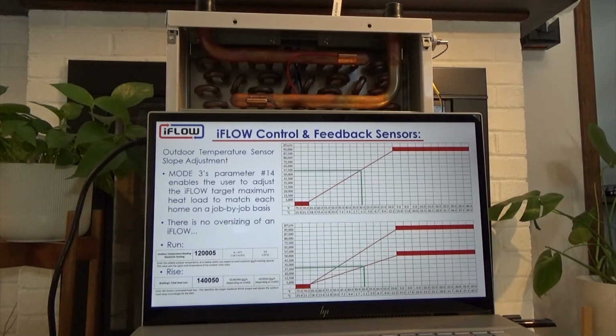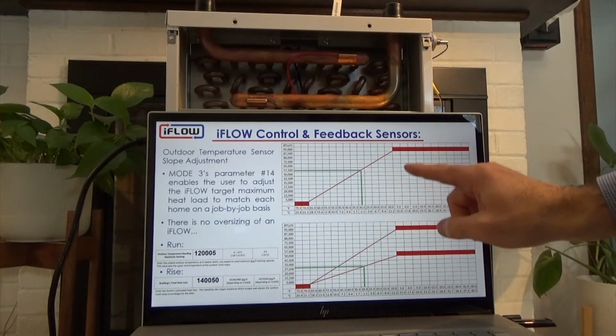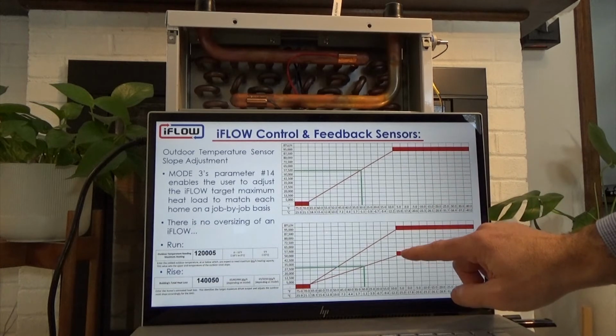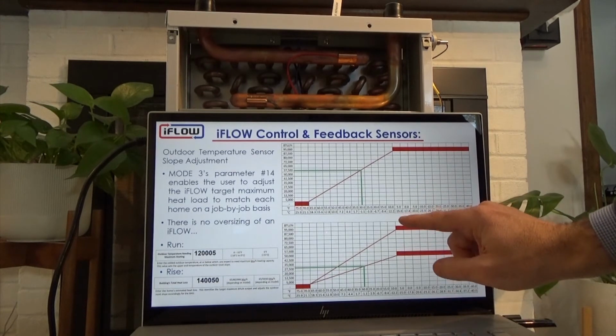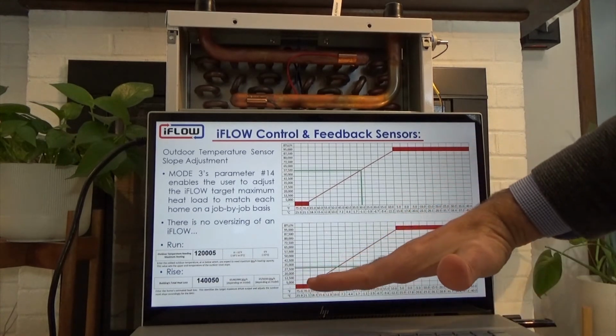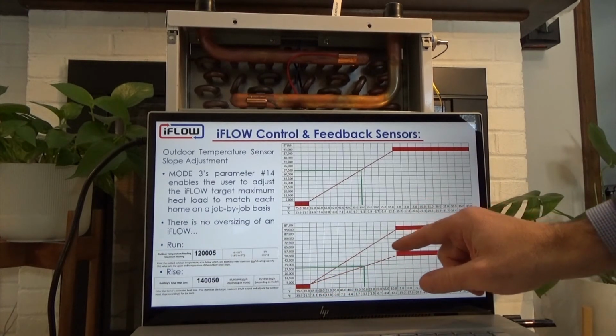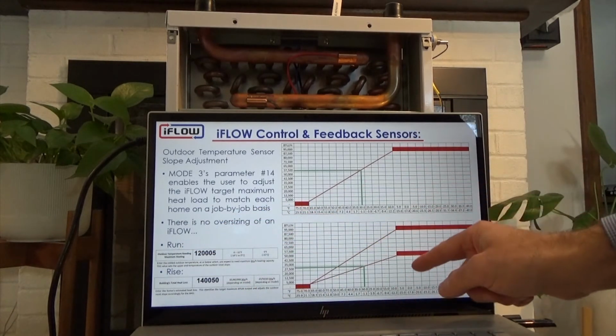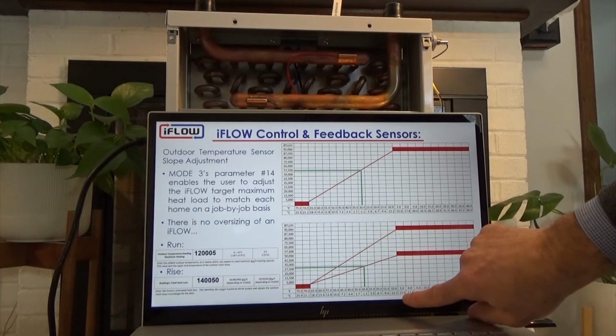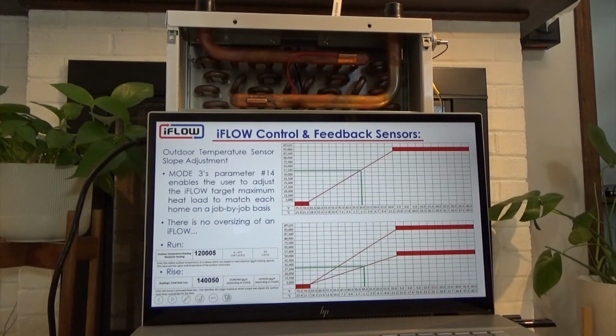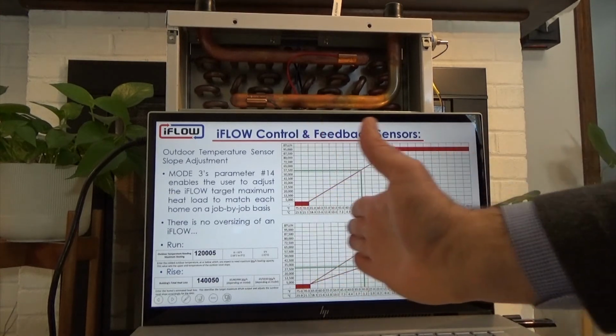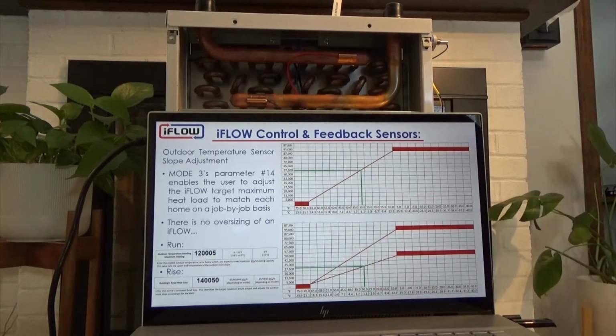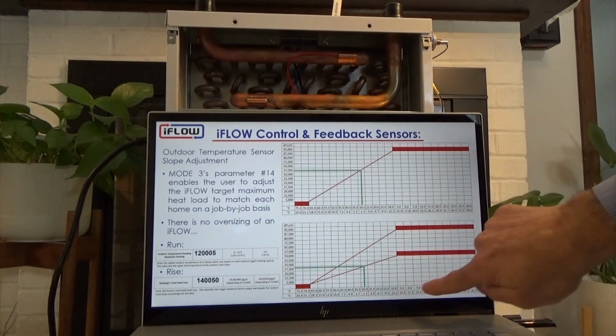So we're basically adjusting, right? You know, a slope, we've got the rise and the run. By adjusting from 95 down to 50, we're lowering the rise. We're flattening the curve. And then with the run, let's assume the run is the same. We're living in the same area, so the outdoor temperature where we need maximum doesn't change. Now, it could change depending on where you are. If you're in California or Texas or Florida or Nebraska or Minnesota, or Alberta, Yukon, Ontario, depending on where you are, this number will change.